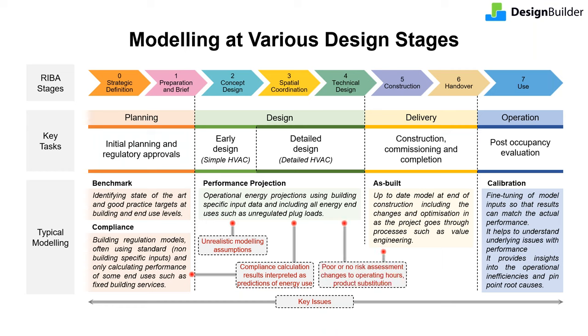When modeling at design stages, it is a common tendency to project energy use as a fixed number without properly assessing the likelihood of achieving it. As good practice, multiple scenarios including likely high-end and low-end energy use should be explored as the design progresses through construction and until handover. Changes in design or proposed constructions occur — such as operating hours changes or product substitution during value engineering — and at relevant stages, especially at handover, the model and projected performance should be updated.